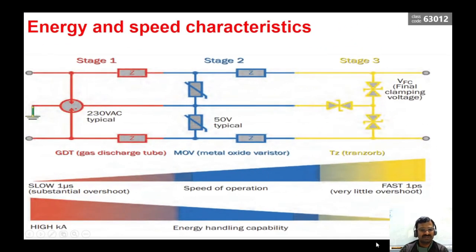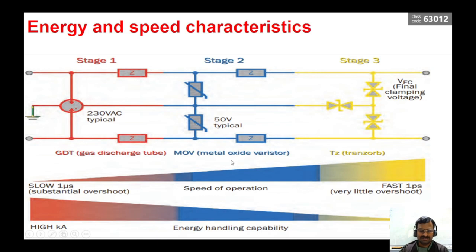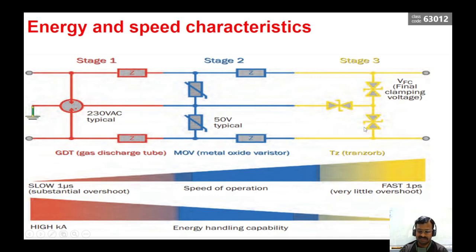Energy and speed characteristics of these SPDs differ at different parts of the electrical power system. On the high voltage side, we are going to have gas discharge tube or spark gap type SPDs — very slow in nature, but they can handle very high current or high surge voltages. At level 2 or type 2, we have metal oxide varistors, where the voltage and current levels are moderate, and speed of operation is also moderate. At the final stage, we have very high speed devices, but the current handling capacity is less — such as a transient voltage suppressor diode, usually called a TVS diode, used in stage 3.